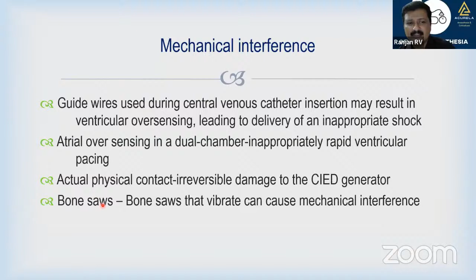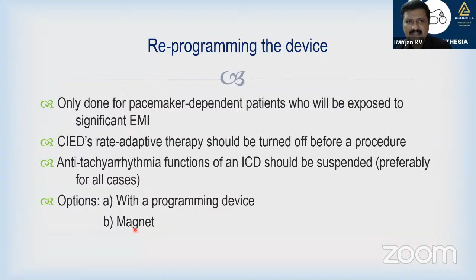So reprogramming, how do we prevent this? It is done in two ways. One, with a programming device, the reprogramming device, which I showed you, the interrogating device. The other is the magnet, which is very simple and easy, which converts any mode into asynchronous mode. Reprogramming with a programming device should be done by trained personnel. You need a big equipment. It will turn both the permanent pacemaker as well as the AICD into asynchronous mode. So this is the advantage.